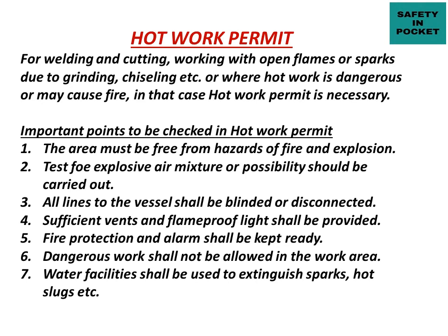Test for explosive air mixture or possibility should be carried out. Air test should be carried out in that area. All lines to the vessel shall be blinded or disconnected. Sufficient vent and flame proof lights shall be provided. Fire protection and alarm shall be kept ready. Dangerous work shall not be allowed in that work area. Water facility shall be used to extinguish spark and hot slugs. So, these are the points in hot work permit, in the checklist all these points should be available for doing the hot work safely and smoothly.